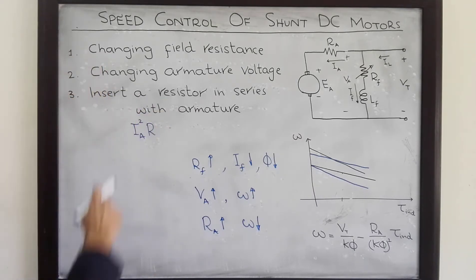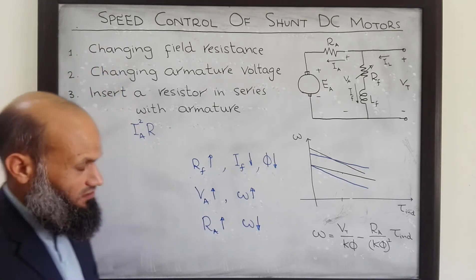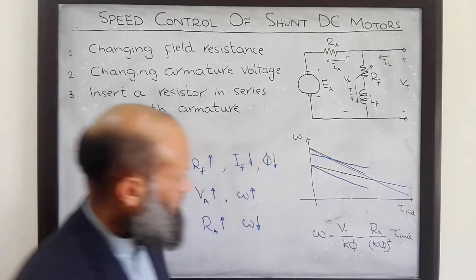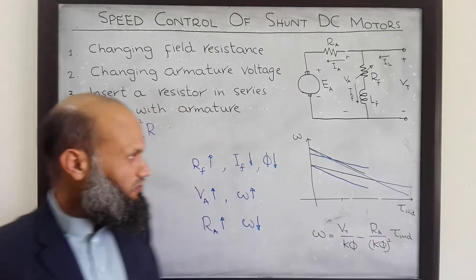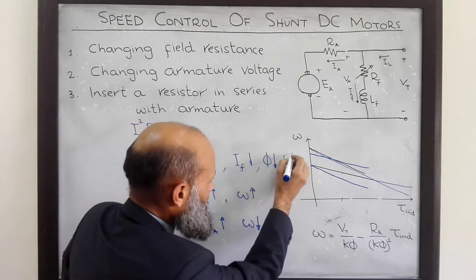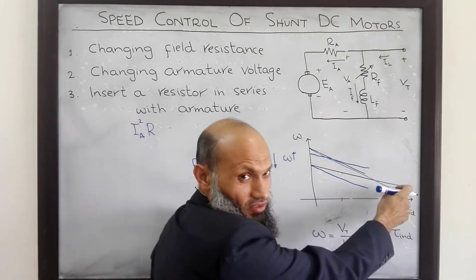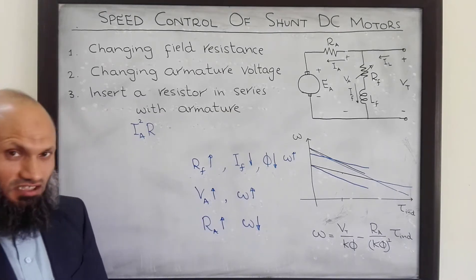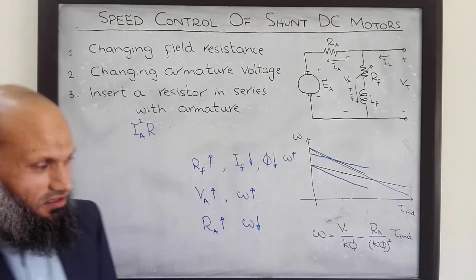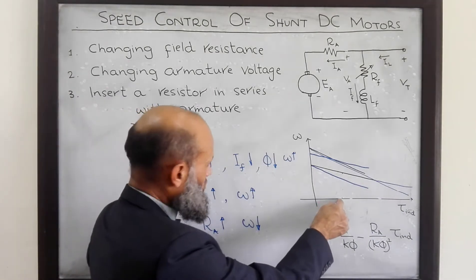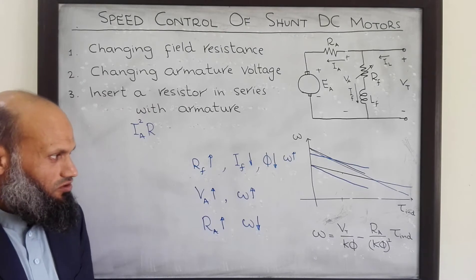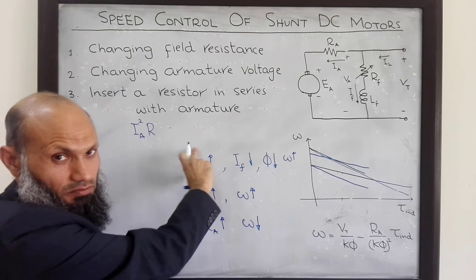Regarding the field resistance approach, if we extend the torque-speed lines, we are not quite sure what will happen with the speed as we increase RF. At smaller loads, an increase in RF is associated with an increase in speed. However, at heavier loads, an increase in RF is associated with a decrease in speed. Since the motor most often runs near the rated load, which is much less than the stall load, in most cases increasing RF will increase speed — but we must be sure about this behavior when using this approach.